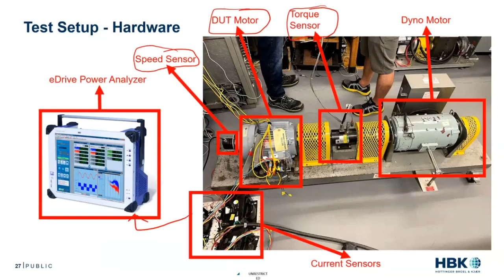So okay, now we need to test that motor. We look at our software interface for that physical motor, and you can see it looks the exact same. We still have that three-phase system, we still have that motor, we still have those efficiencies, our squiggly lines look the same, our meters look the same. So we're using the exact same test setup. Let's look at the sensors for that motor.